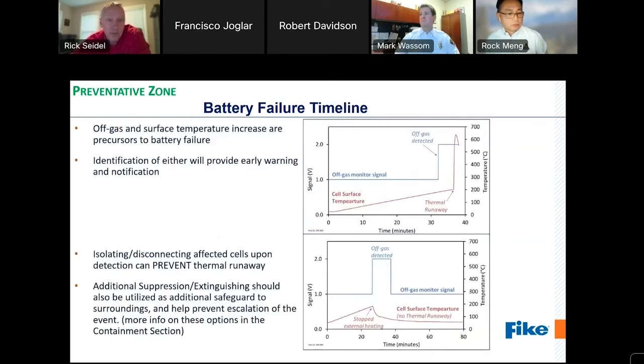Next, please. And specifically testing off-gas detection performance. The graph at the top of the screen shows an uninterrupted battery failure where off-gas was detected at approximately 32 minutes. The external heating continued and thermal runaway occurred about 5 minutes later. In the lower graph, upon detecting the off-gas, the battery management system was programmed to disconnect that cell from the circuit, and almost immediately after stopping the external surface heating, the surface temperature decreased and thermal runaway did not occur.